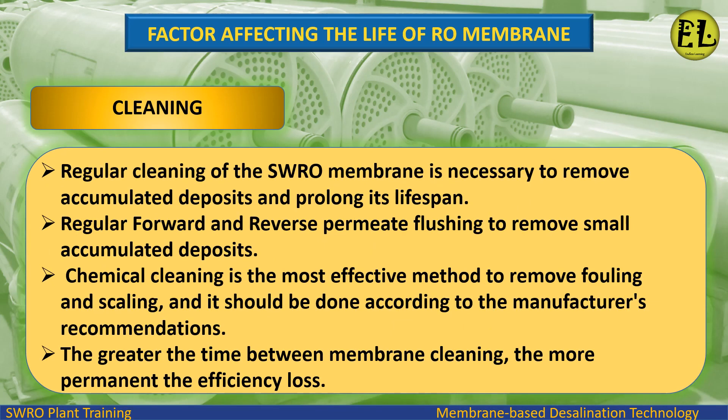Regular cleaning of the SWRO membrane is necessary to remove accumulated deposits and prolong its lifespan. This includes regular forward and reverse permeate flushing to remove small accumulated deposits. Chemical cleaning is the most effective method to remove fouling and scaling, and should be done according to the manufacturer's recommendations. The greater the time between membrane cleanings, the more permanent the efficiency loss.